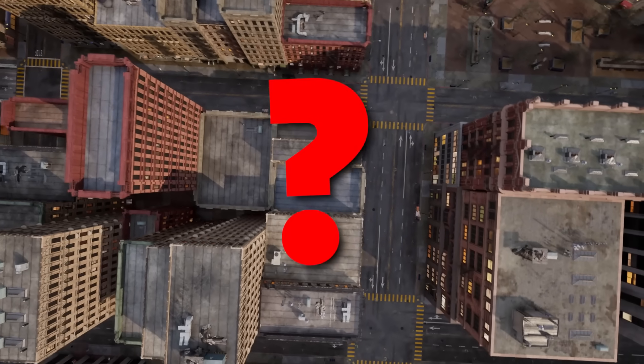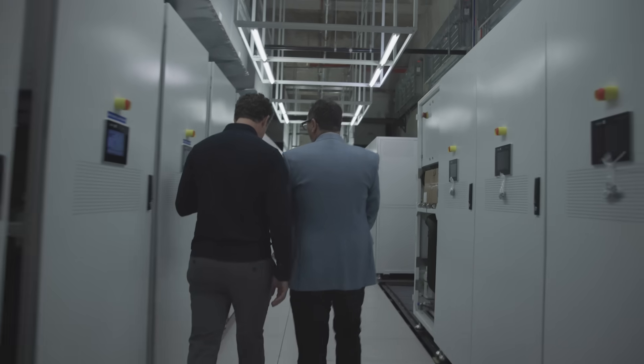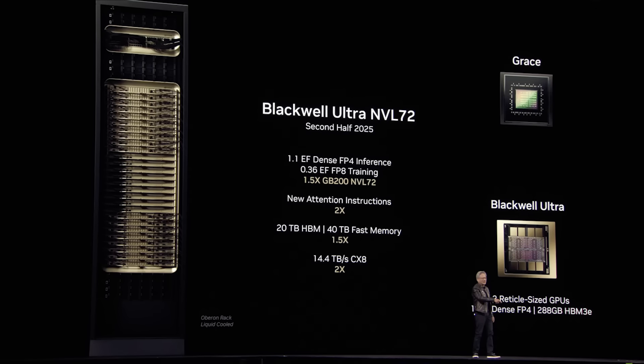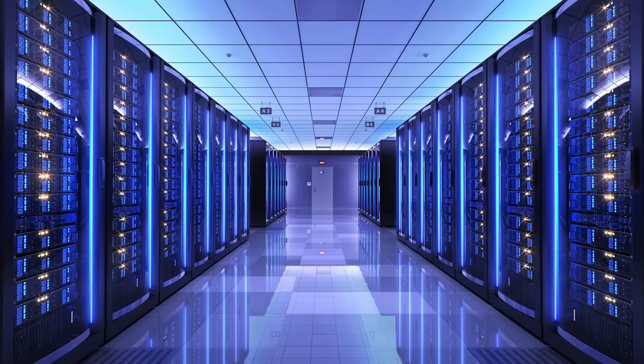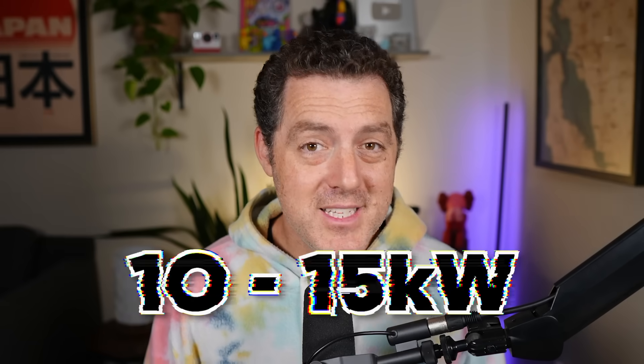As companies like Google, OpenAI, and Microsoft think about where to place their next data center, primarily they're asking: how are they going to generate enough electricity to power all of their chips? Then we have the actual racks — metal frames that house all of the GPUs. These new AI racks are monsters. NVIDIA's Rubin-era systems will likely get up to about 600 kilowatts per rack later this decade, which is 5 to 10 times what a conventional rack gets today. Today's high-end clusters already get between 80 and 120 kilowatts per rack, compared to just 10 to 15 kilowatts a few years ago.